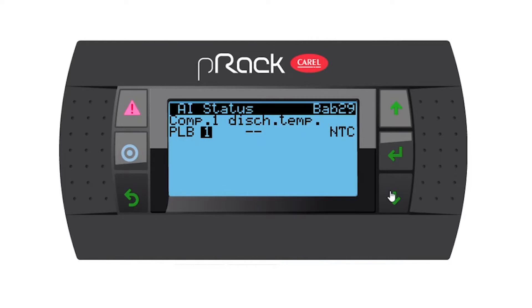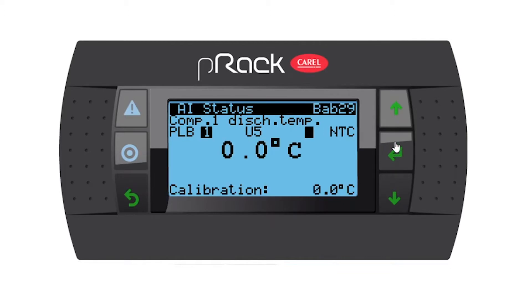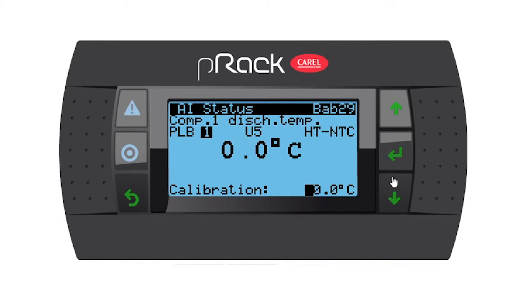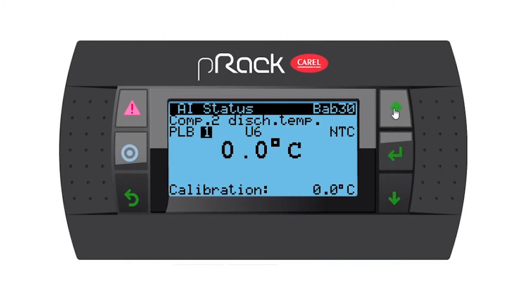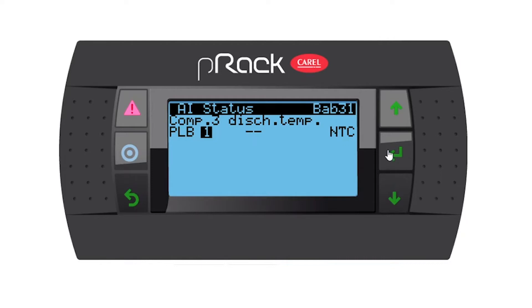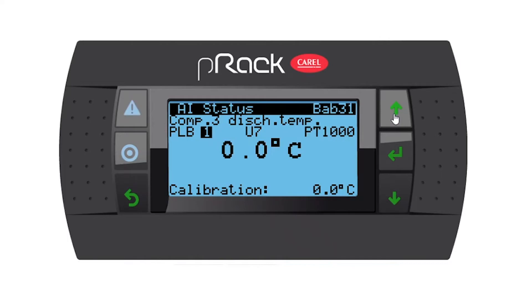Going down — discharge pressure or compressor one discharge temp? Yes I do, so I'm going to assign it to U5. I'm going to make it an HT NTC, which is the high temperature version, with zero calibration. Compressor two — I'll do the same, assign it to U6 and make it an HT NTC. The next one I'll assign as well and make it an HT NTC with zero calibration.